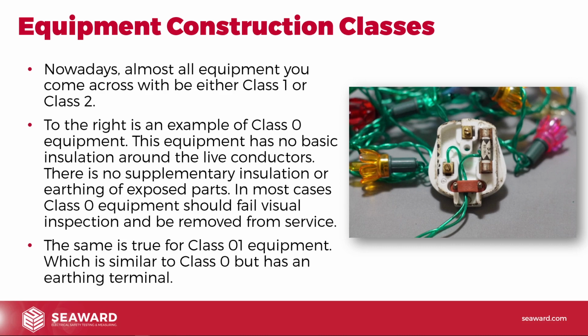So you can see here this typical example of Class 0 equipment. We've got a picture there of these old Christmas tree lights, and you can see that we've got the live conductors inside the cables, and we've just got this sort of transparent green insulation on the outside of that. There's no sheath for providing mechanical protection. There's no earthing of any exposed parts. There's no double insulation in there. All we've got is 230 volts separated from us by that green transparent insulation. So you can imagine if we had a nick in that green transparent insulation, straight away we could touch live parts and there wouldn't really be anything there to protect us. So again, nowadays generally seen as dangerous equipment, and usually failed straight away on site and removed from service.